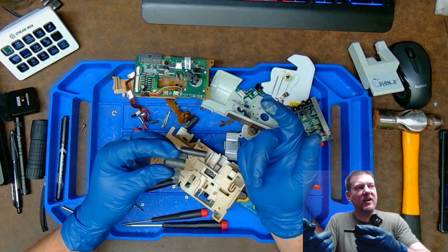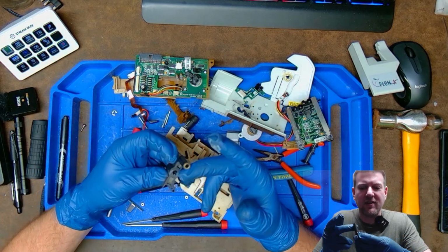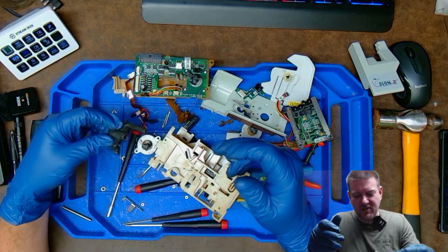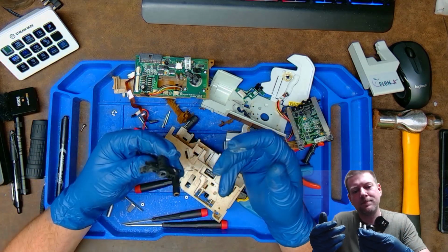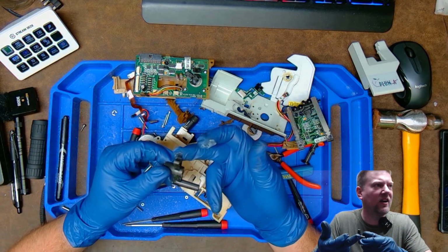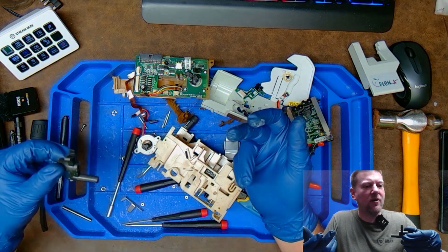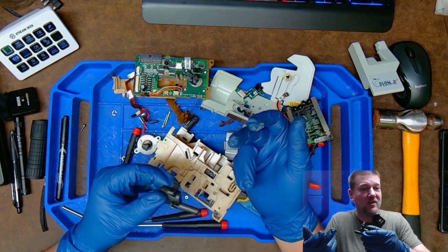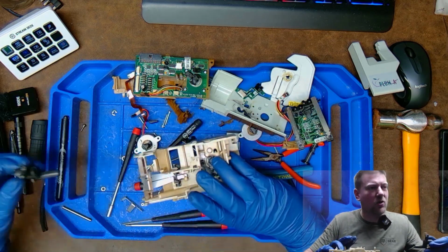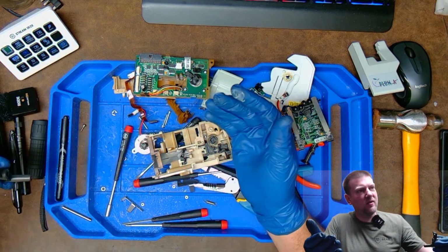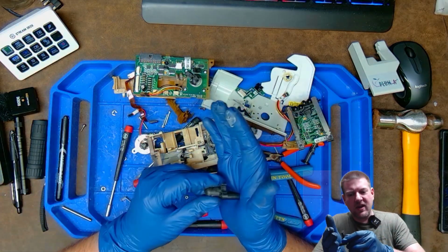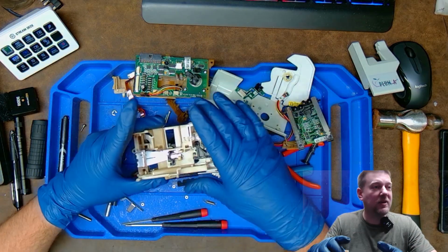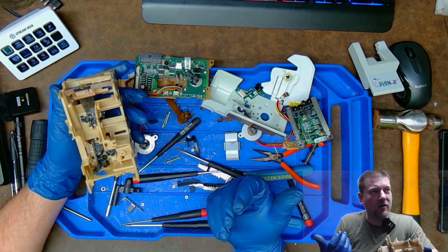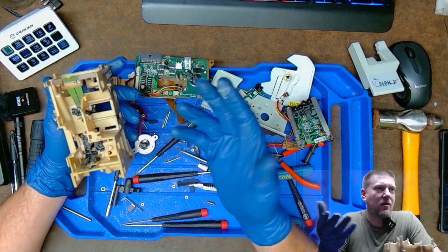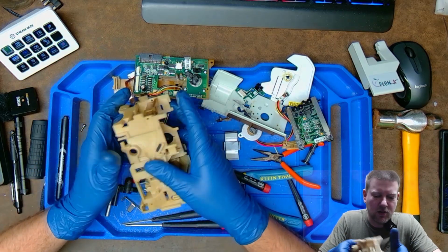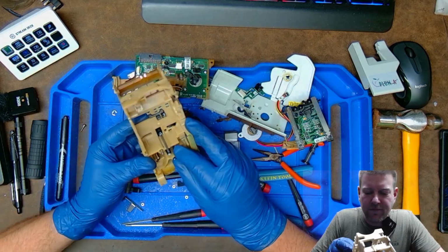So this right here is the plunger that actually does the pumping. It's very specific. There's a bronze oil bushing that it rides on that keeps it linear, nice and smooth. And there's that flag right there that detects when it goes all the way out or when it goes all the way into its home position. I think on this one, it's all the way in. So it goes all the way out to push the fluids, and it goes all the way in. That's at its home position. So it has to be at the home position when you open the door, because that way you can load the set without opposition, right? You gotta be able to easily load the calibration set or the infusion set.